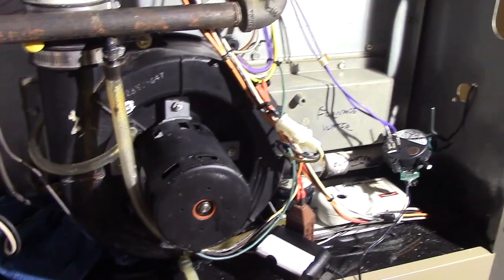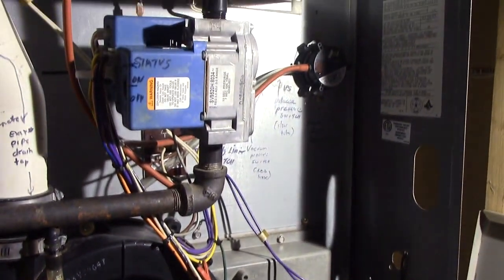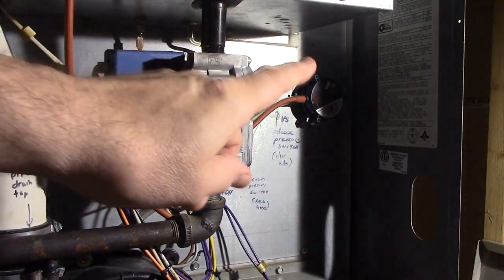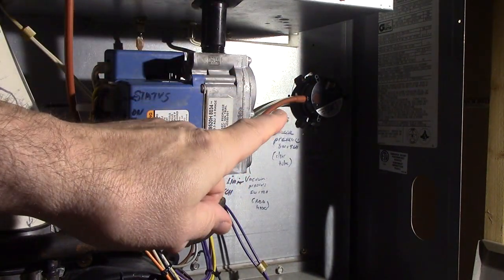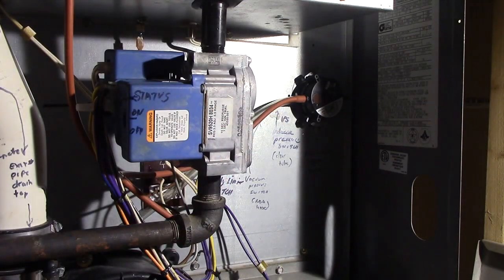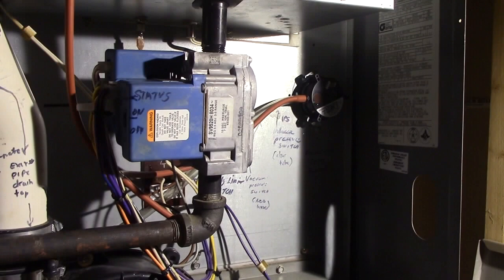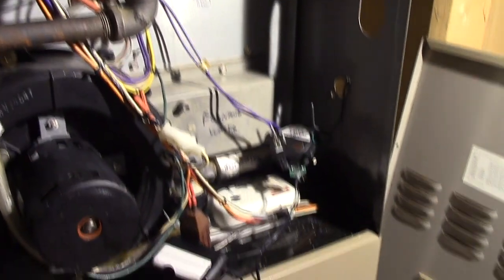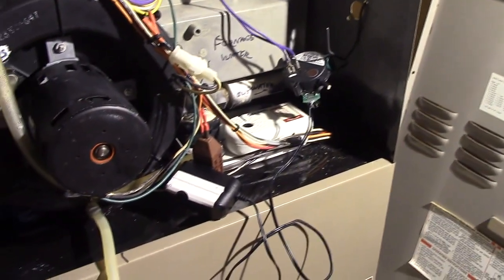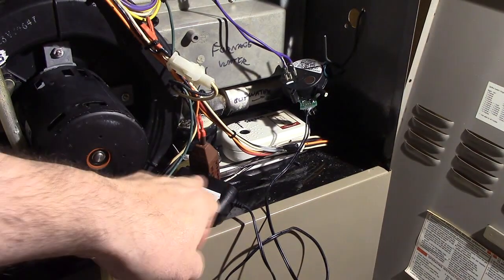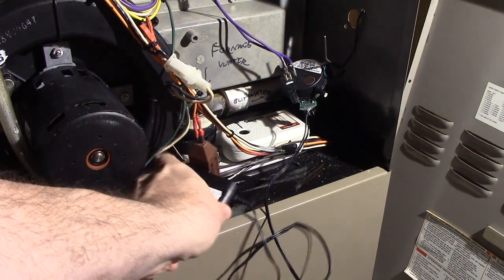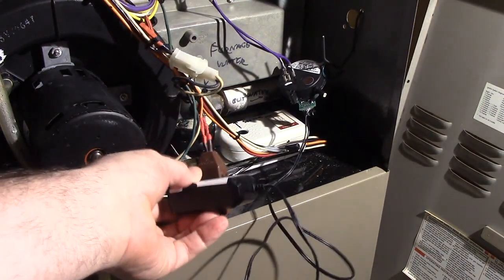Now, that pressure switch is located on this furnace right there. You can see it's not connected, but yet my furnace is working because what I did here is I designed a circuit.